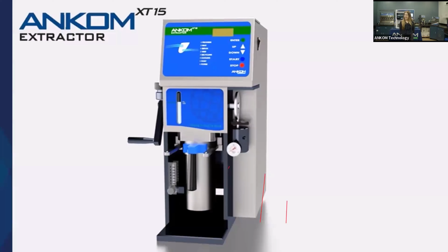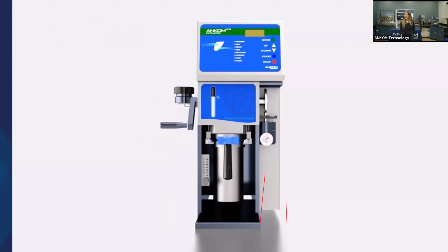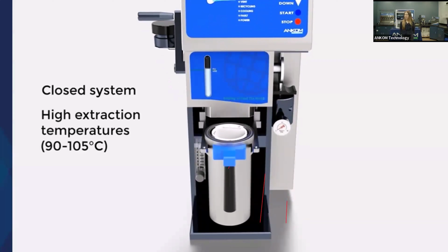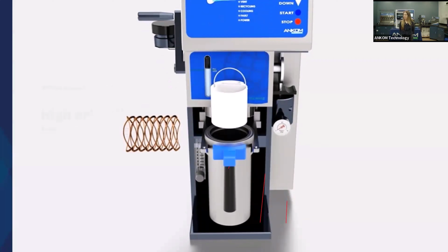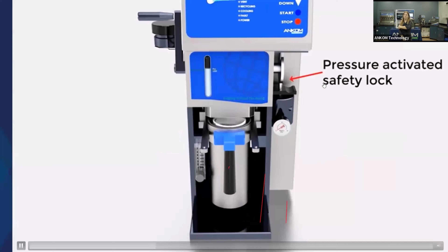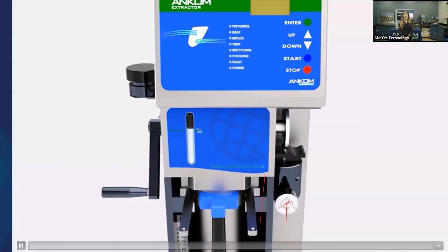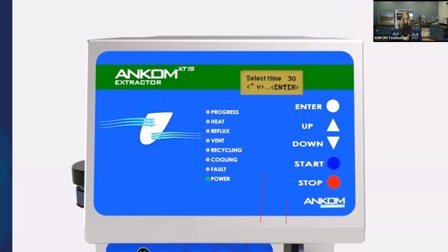The ANKOM XT15 extractor advances and simplifies the conventional Soxhlet operation. The XT15 automates the process in a closed system. 90 degrees Celsius extraction temperatures accelerate kinetics to greatly reduce extraction times. With the ANKOM XT15, samples are prepared and encapsulated in a specially made filter bag. Up to 15 samples are placed in the extractor. After selecting the extraction time and closing the extraction vessel, the user pushes the start button and the system automatically controls the entire process.